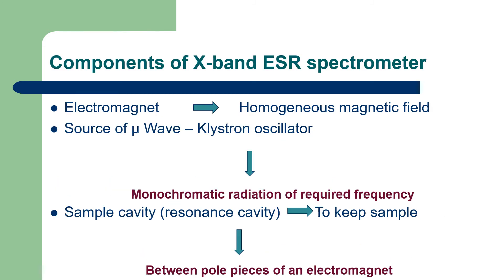Now, let us consider the different components of X-band ESR spectrometer. The first important component is an electromagnet that should produce homogeneous magnetic field. Second one is a source of microwave. Usually, we use klystron oscillator as the source. Klystron oscillator will produce monochromatic radiation of required frequency.